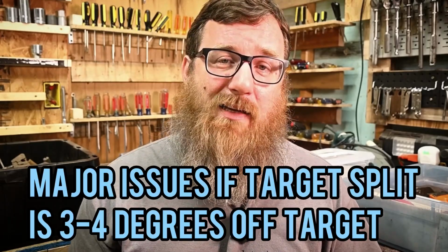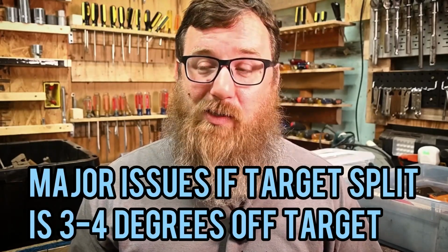It's pretty simple, and it'll give you a lot better idea if your airflow is doing okay, too much, which is usually never the case, too low, or your system may have an issue if you have a low split when your target is higher.